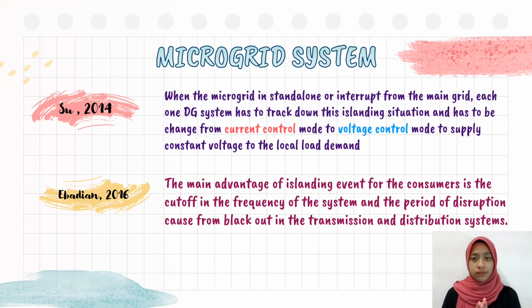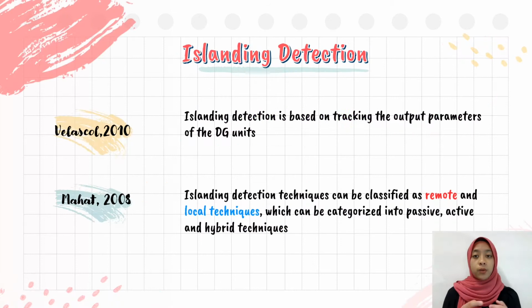I have discovered one article written by Su in 2014. She stated that when the microgrid is stand-alone or interrupted from the main grid, each DG system has to track this islanding situation and change from current control mode to voltage control mode, so it can supply constant voltage to the local demand. We already know what islanding is, but how to detect islanding?